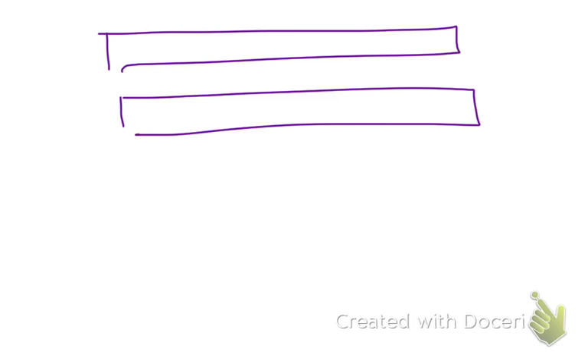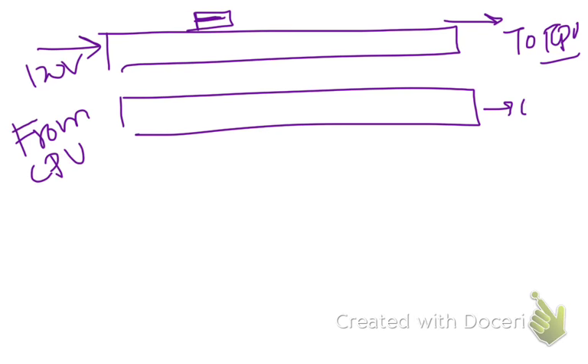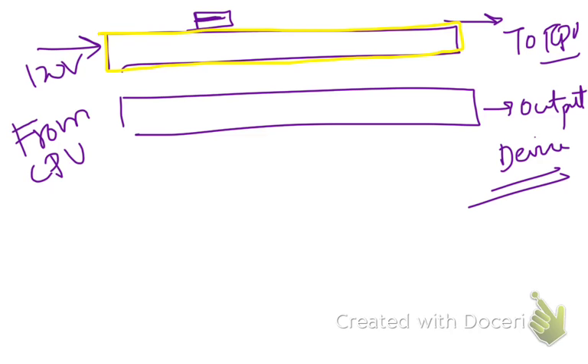Now, another point to note about this input and output modules is, we have seen two circuit diagrams for input and output logics. For input logics, it was from the 120 voltage AC, then optical isolator, and then we had the output to CPU. And for the output module, it was from CPU to the output device. Now, what I would like to tell you is, in any PLC system, never a single terminal is used. For example, what the circuit diagram we saw was just a single terminal. Usually, for input modules, we have 4, 6, 8, 12, 16, 32 terminals.